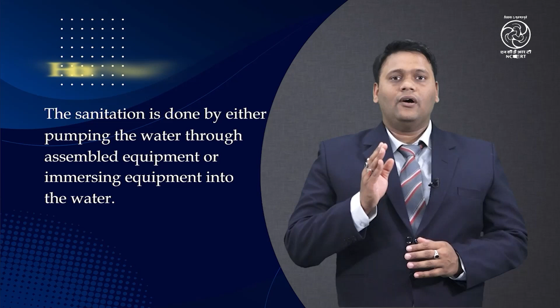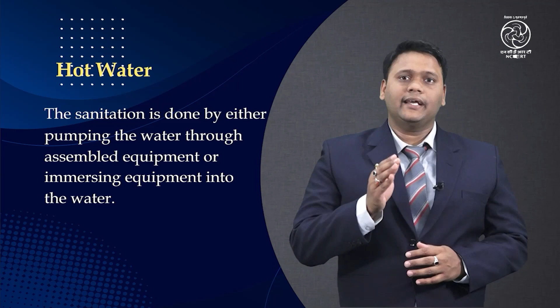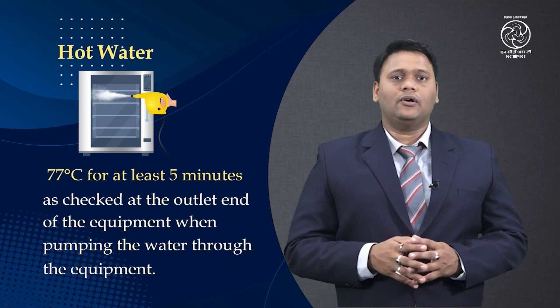In hot water type sanitization methods, the sanitization is done by either pumping the water through assembled equipment or immersing equipment into the water. The temperature is maintained at 77 degrees Celsius for at least 5 minutes as checked at the outlet end of the equipment when pumping the water through the equipment. When immersing equipment, the temperature of water is maintained at 77 degrees Celsius or above for at least 30 seconds.